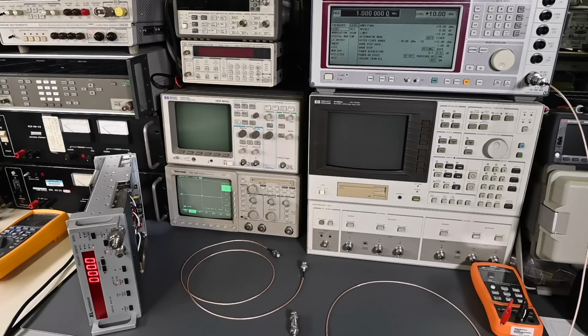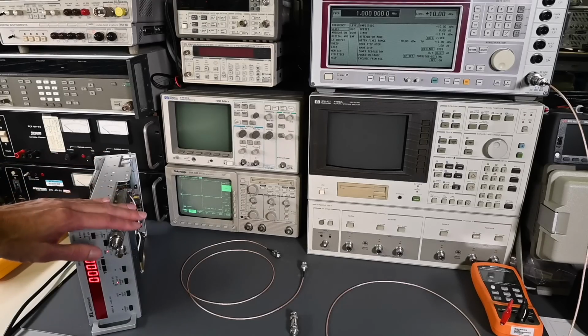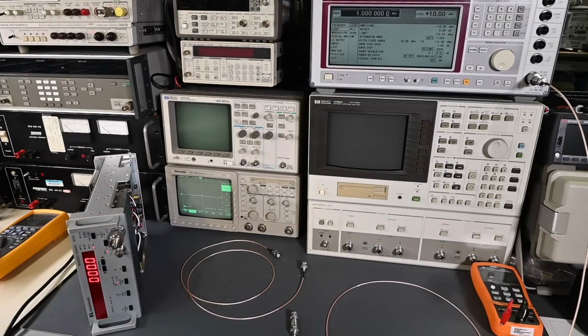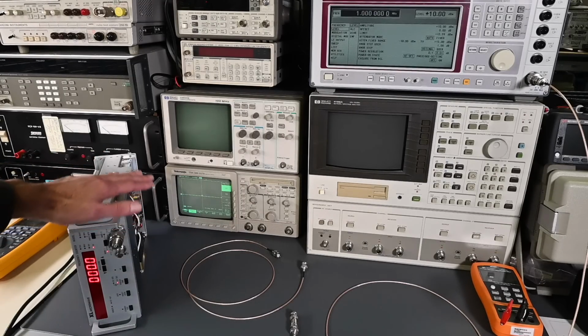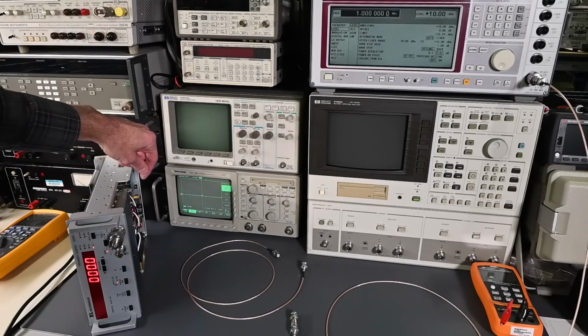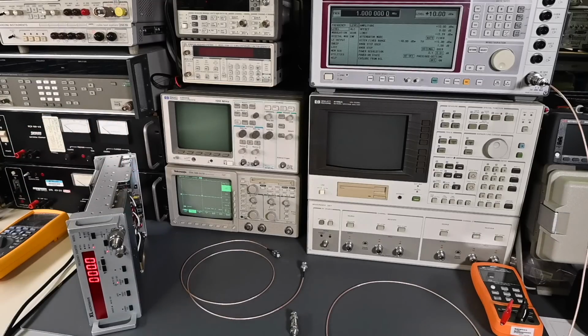Now, I'm not going to cover that in this video because I've already shown that in another video where I do the calibration on a Hewlett-Packard 5334B frequency counter. So if you're interested in seeing how that time base is calibrated, definitely check out that other video. Just keep in mind that when you are doing calibration on an internal time base on a frequency counter, the external time base that you're using for that calibration needs to be extremely accurate and stable, because otherwise your calibration and your frequency counter is going to be all over the place. Also, when this internal time base is adjusted, the covers need to be installed. There's a little hole in the bottom cover. You reach through that, and the adjustment is on the circuit board right here.